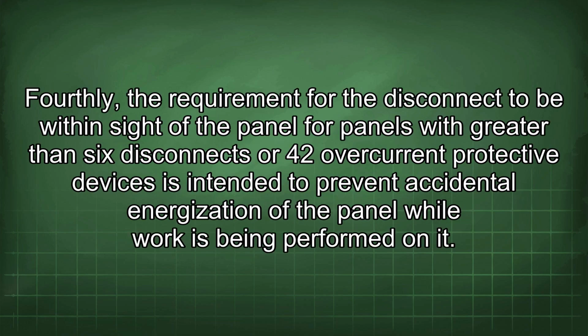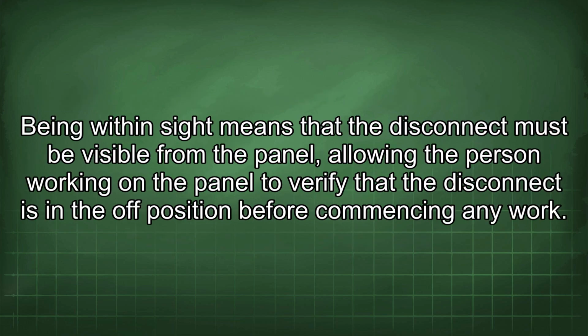Fourthly, the requirement for the disconnect to be within sight of the panel for panels with greater than 6 disconnects or 42 overcurrent protective devices is intended to prevent accidental energization of the panel while work is being performed on it. Being within sight means that the disconnect must be visible from the panel, allowing the person working on the panel to verify that the disconnect is in the off position before commencing any work.